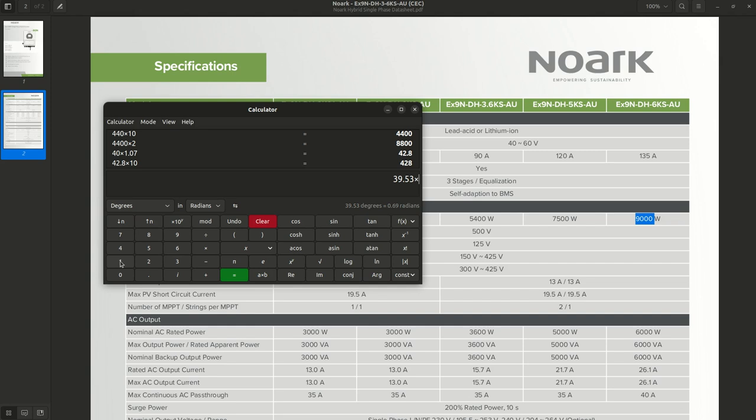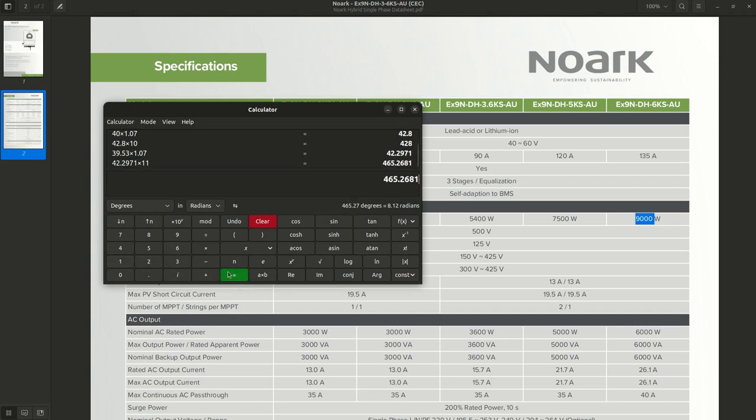Now, we multiply this figure here just because of a temperature coefficient. That's a climatic thing. And then I'll multiply that by about 11 panels. That's under the 500 volts. That's the most you'll get.